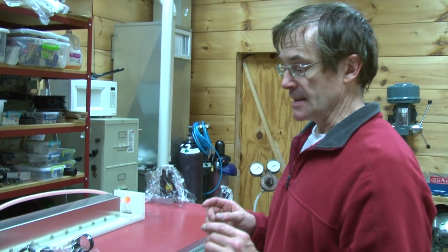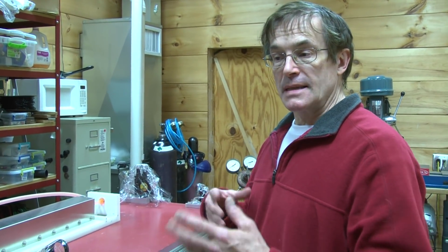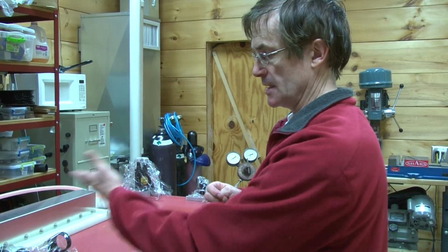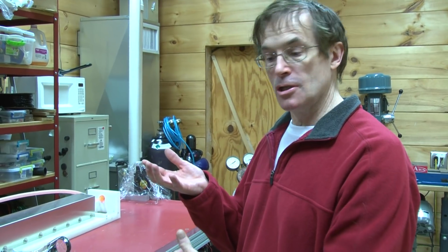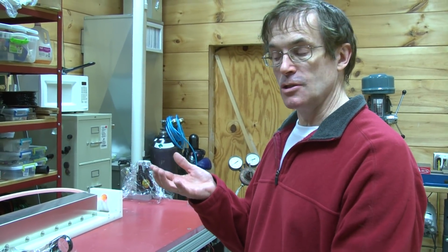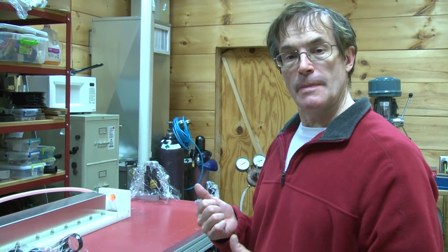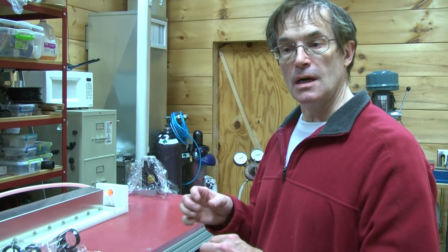You also want a very high voltage capacitor, because based on the LC circuit design of any discharge system, there's a floor to how low you can get the self-inductance—mechanically you're just limited. By discharging the same amount of energy at a higher voltage but lower capacitance, you increase the speed of the discharge. So low inductance and high voltage are specifically what discharge capacitors are made for: very rapid loss of voltage and very rapid discharge mechanical forces.